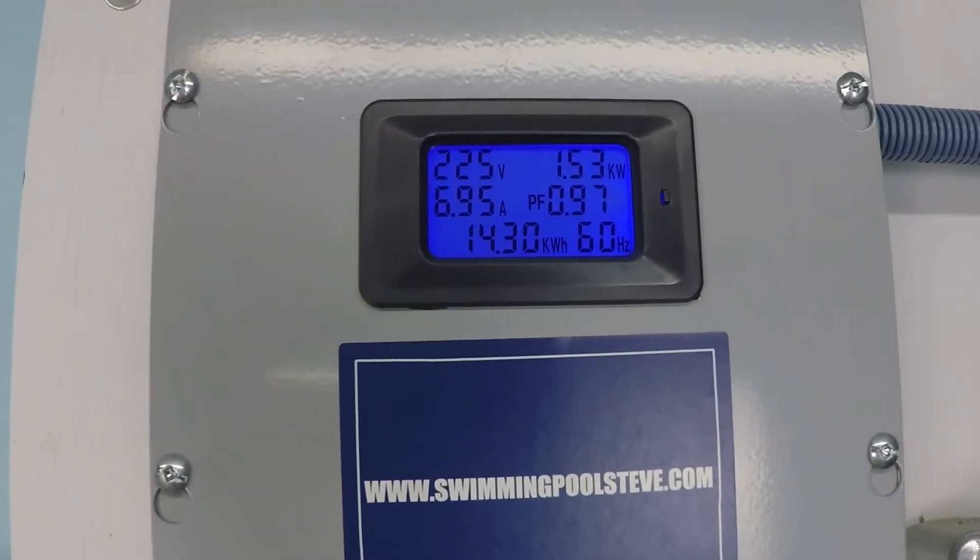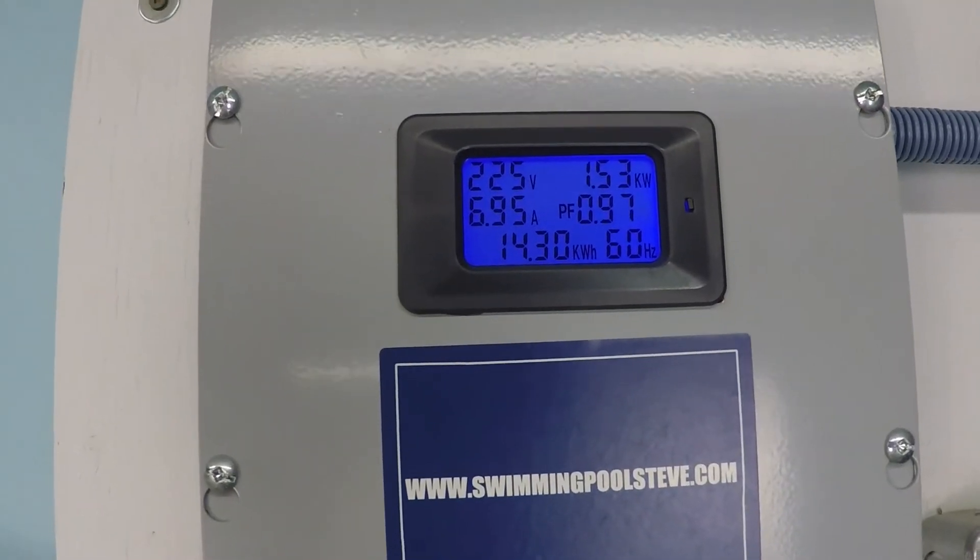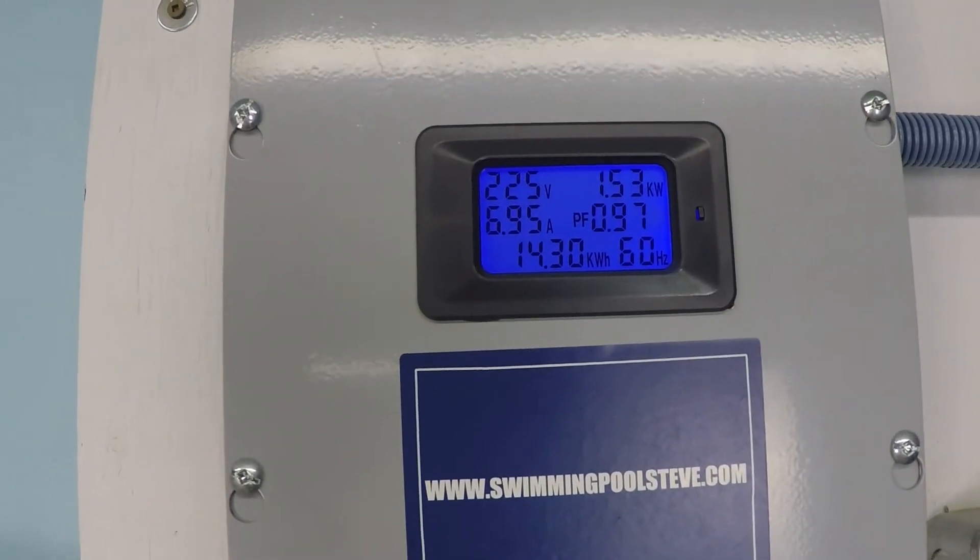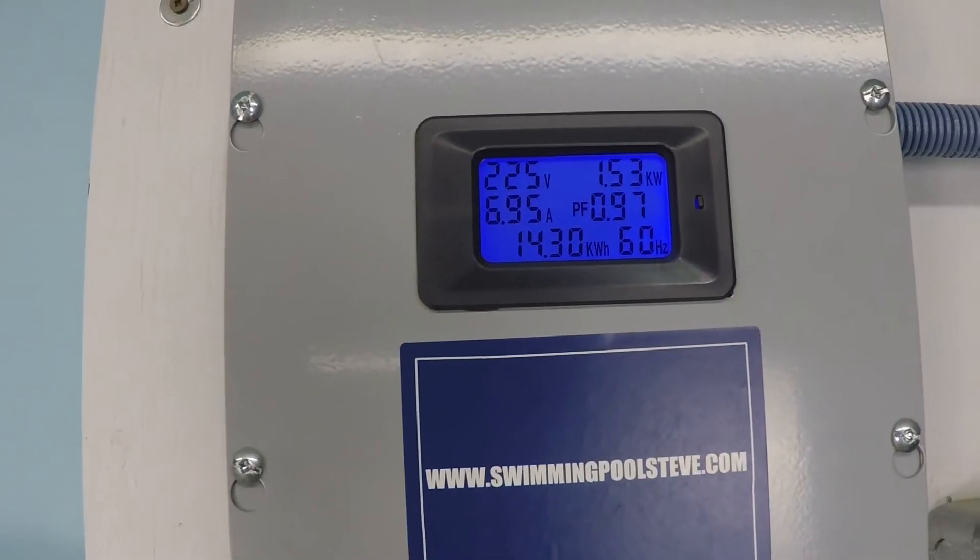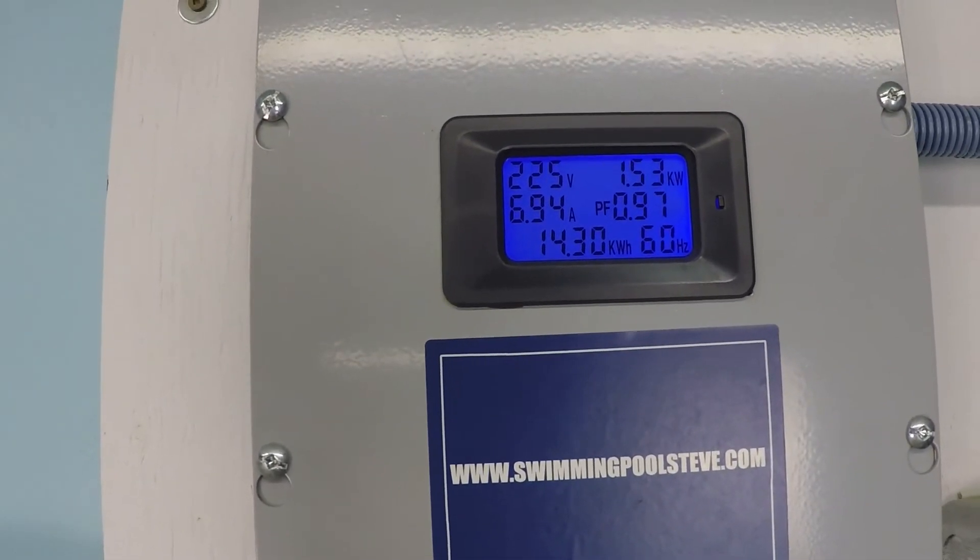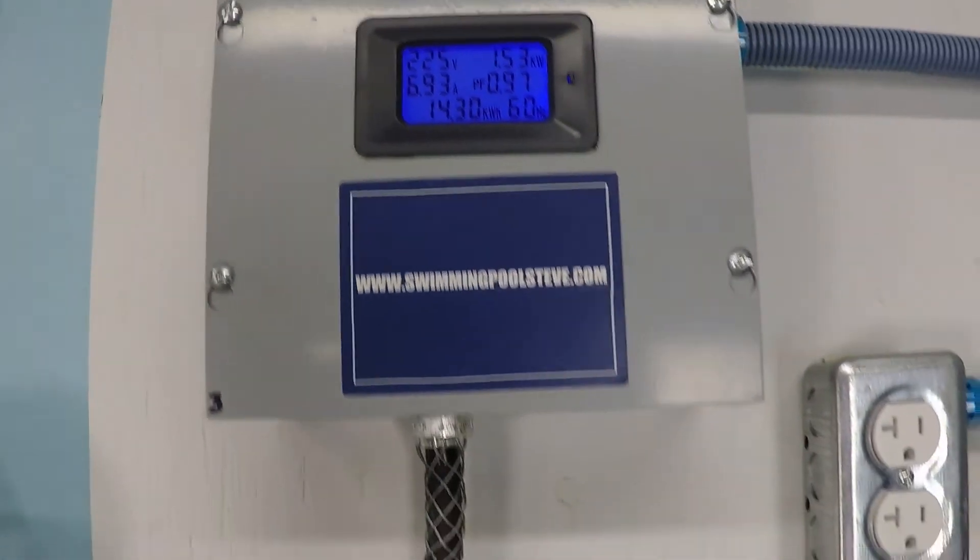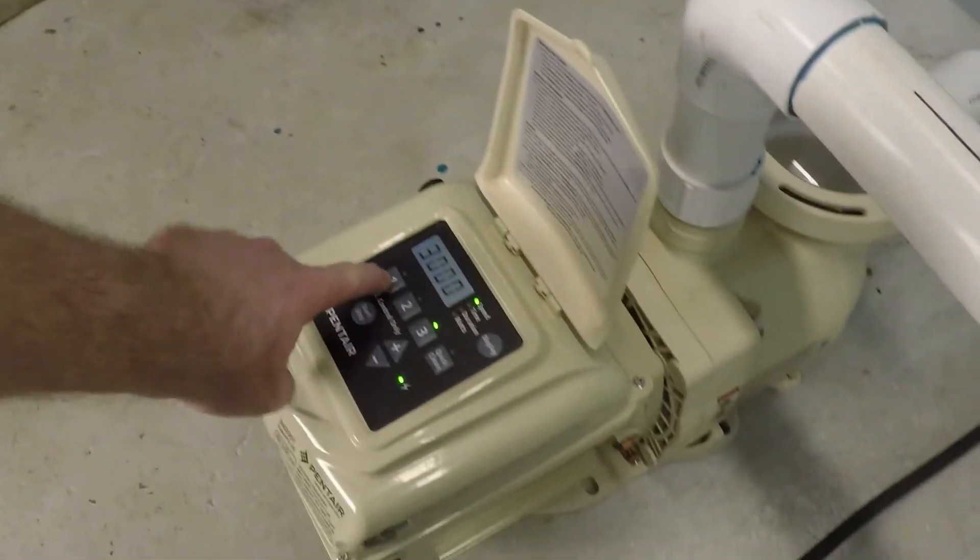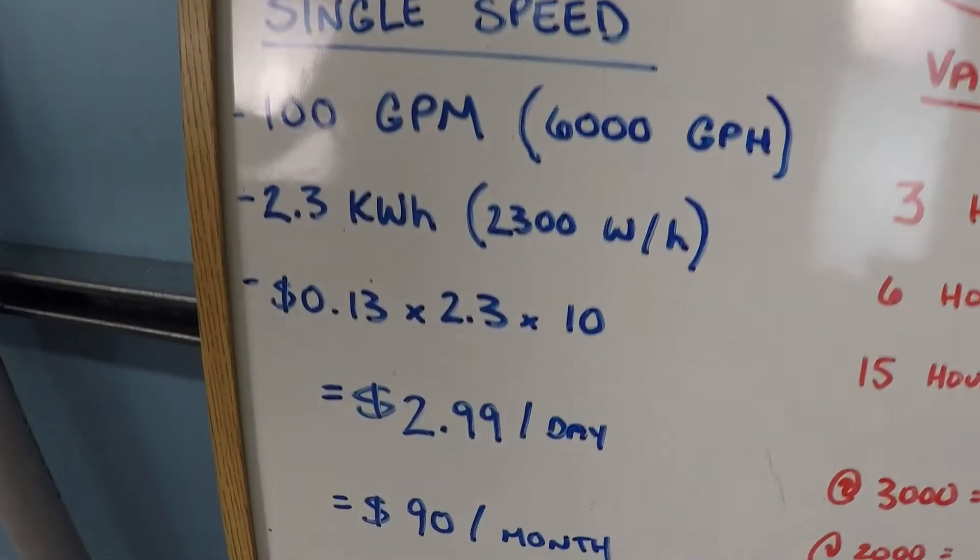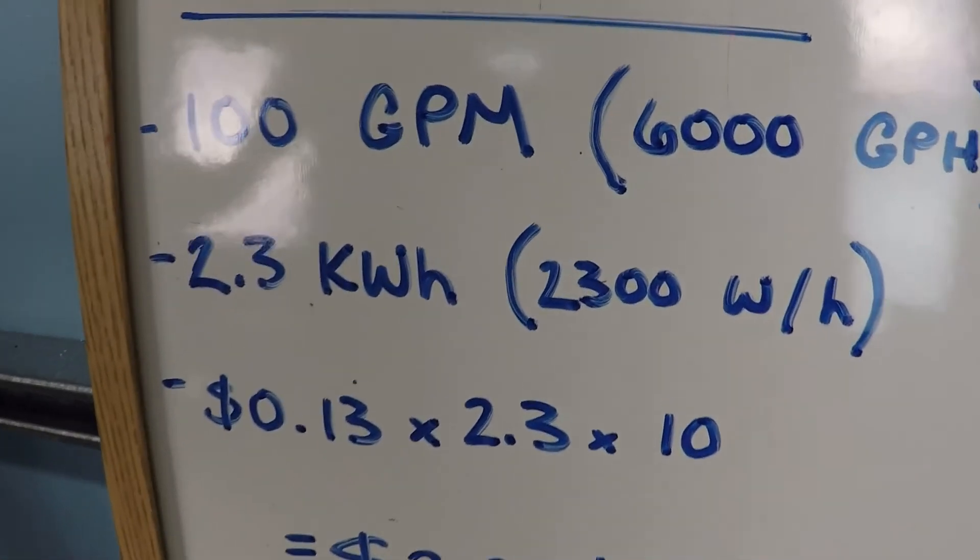86 gallons per minute. 1.53 kilowatts, 1,530 watts, 6.94 amps is the current draw.